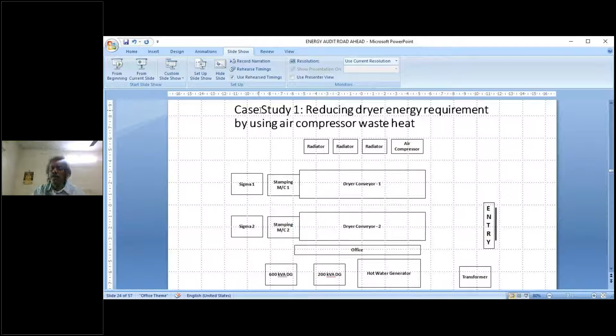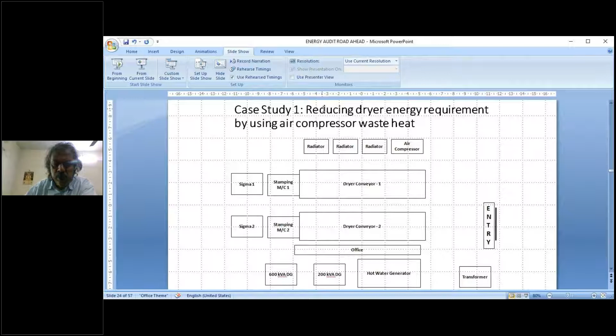Now once we know this, there is heat available from the compressor. There is a heat requirement in the dryer. How to integrate? You can put a heat exchanger in the air compressor and take that hot water and use it for the drying energy requirement. So this is a simple way of integrating. In this case, the focus is not on the boiler, it's on the production. There is a requirement for heat in the dryer. There is heat available in the air compressor.